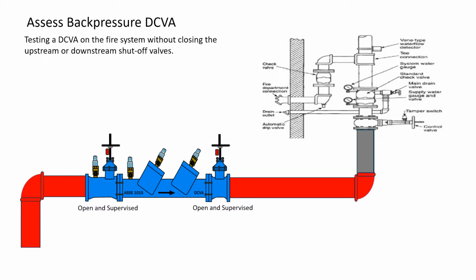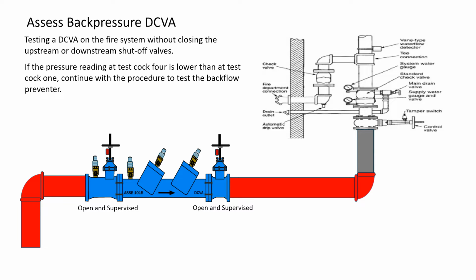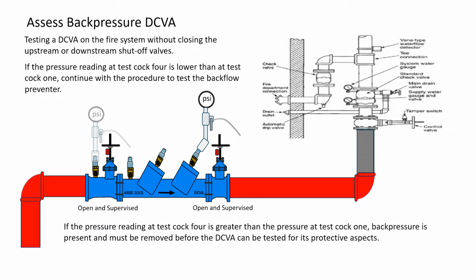Testing a DCVA on the fire system, without closing the upstream or downstream shutoff valves. If the pressure reading at test cock 4 is lower than at test cock 1, continue with the procedure to test the backflow preventer. If the pressure reading at test cock 4 is greater than the pressure at test cock 1, back pressure is present, and must be removed before the DCVA can be tested for its protective aspects.